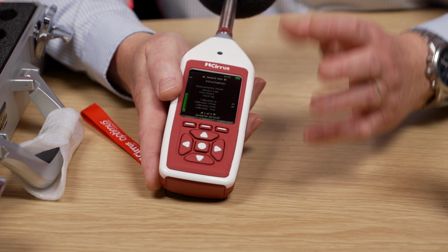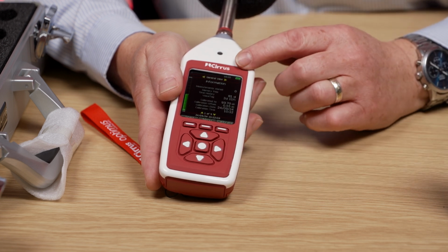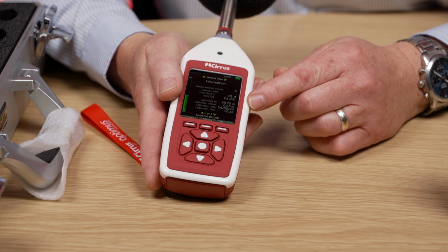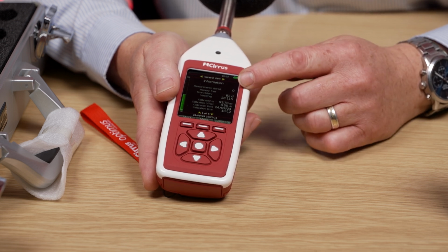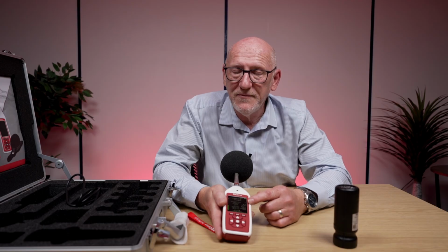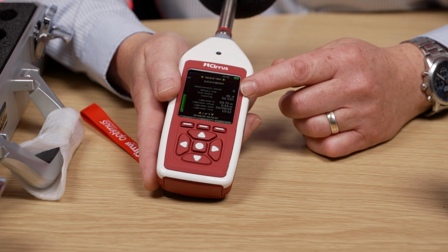And then finally, on this particular meter, we have a general view screen, and this is telling us information about our instrument. I've got no measurement stored at the moment, that's 0 because I've not used it yet. I've got plenty of time history. So on the Optimus Plus we've got 81 days we can store data for continuous measurements. It's a huge capacity.